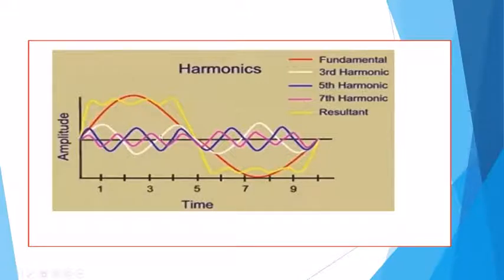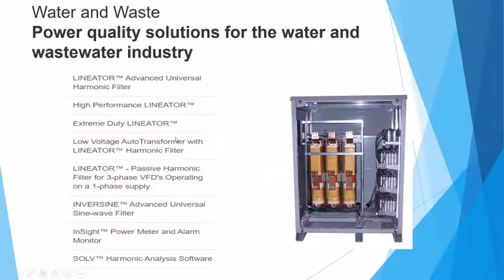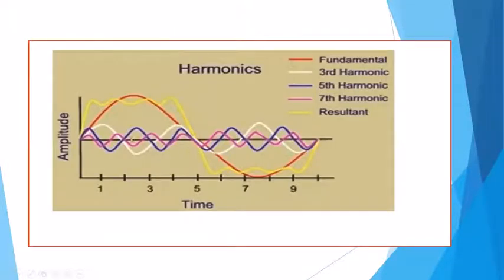And so you get all of these various harmonic amounts that come off of the original voltage waveform, and these are again 3rd, 5th, 7th harmonic. You can see these percentages, but then the meter actually counts that resultant amount of power. So from that, they've had to come up with all these fancy filters to try to eliminate them. So again, it's more coils, more capacitors. This happens to be an input line or line reactors and input harmonic filters that eliminate these noises. They basically get the resultant.